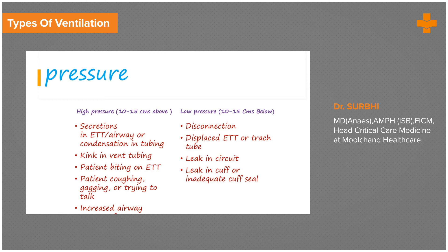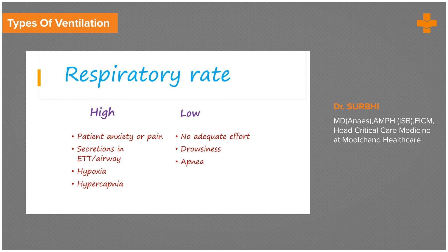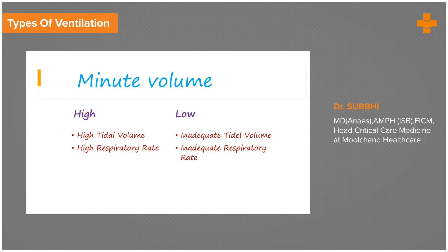High pressure alarms are caused by secretions or a block in the airway, a kink in the ventilator tubing, the patient biting, coughing, or increased airway pressures due to bronchospasm. Low pressure alarms are usually due to disconnection, a leak in the circuit, a leak in the cuff, or a displaced endotracheal tube. High tidal volume and high respiratory rate alarms are also important to monitor.